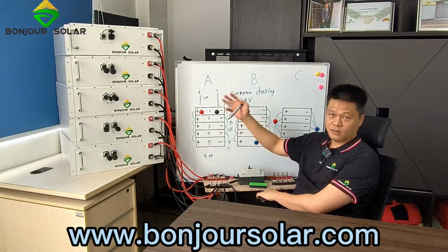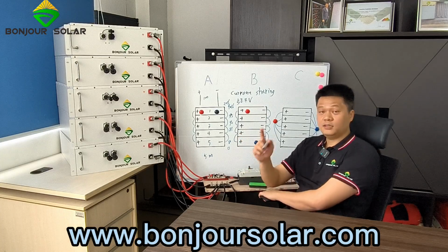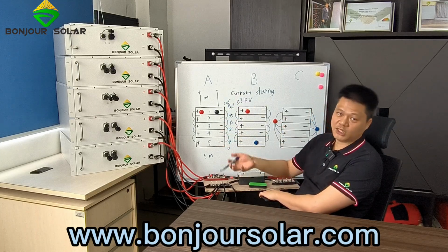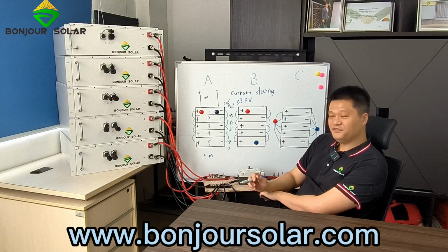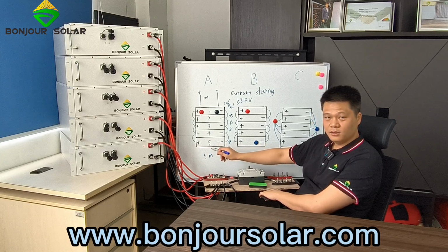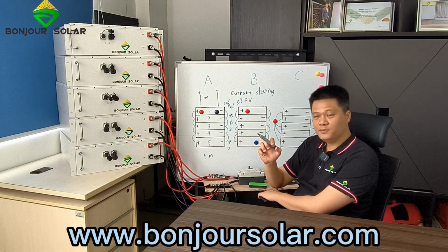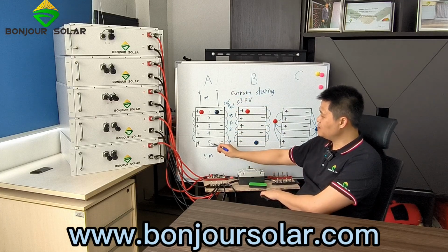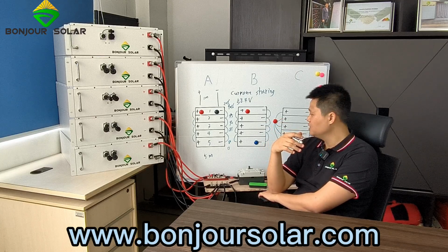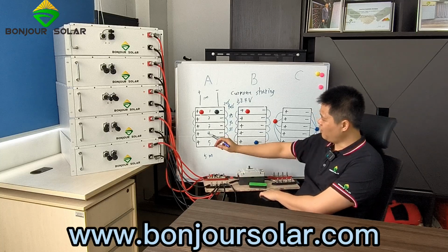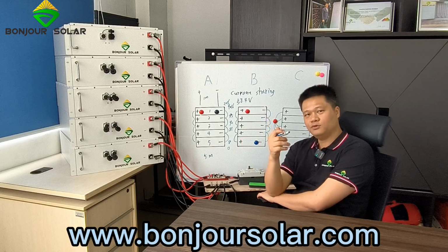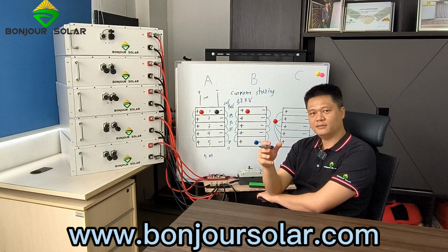That means the battery is not balanced, and this is for one-time charging and discharging. So you can imagine, if every day they charge and discharge like this, in a few months later the number 5 battery's capacity will be very, very low, and they always discharge, and sometimes number 5 may be over-discharging. That will be not good for not only number 5, but also the whole system, the whole lithium battery. You cannot use 100% of the lithium battery capacity.